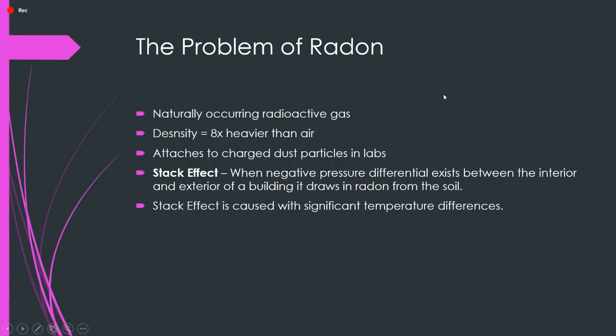So yeah, radon's a problem because when I run a sample in our LSC, sometimes it'll come back at action level. And action level is when we have to go and remove contaminants. But whenever something like that happens, to know for a fact that yes, that is contaminated, and to account for the problem of radon, I will rerun a sample. If it comes back above action level, I'll run it 2 more times, and then I take the average. The average tells me, is it really contaminated? If not, it was radon.